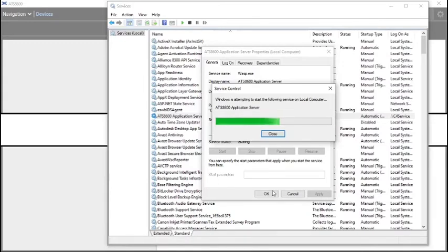Note that I have restarted the entire PC at this stage, and it also didn't fix it. The only thing that constantly fixed this mistake was keeping the ATS open with the Fire panel and restarting the service with the two devices open, or the device and the software open.